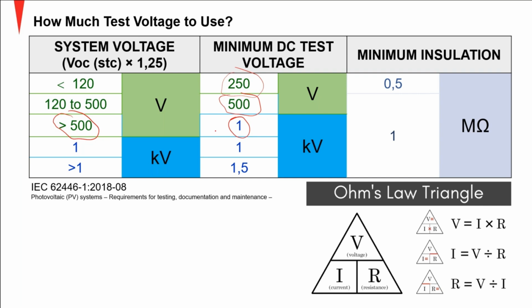And if you have a system that is at 1 kilovolt, you want to use 1 kilovolt, and above that, 1.5. And the minimum insulation result that you should get is 1 mega ohm for systems higher than 120. For systems below 120, you could have 0.5 mega ohms, or 500 kilo ohms. Now, the higher this value or this result, the better. And it depends on how big the system is that you're testing.